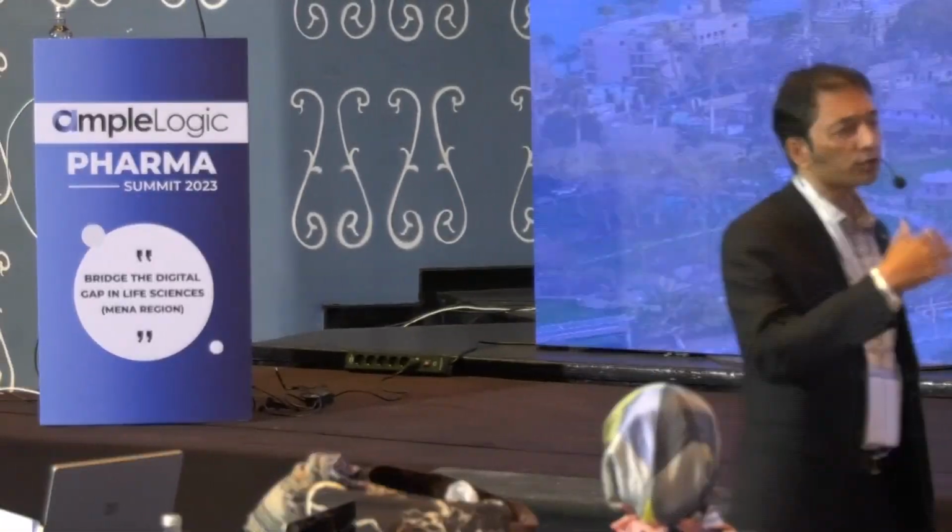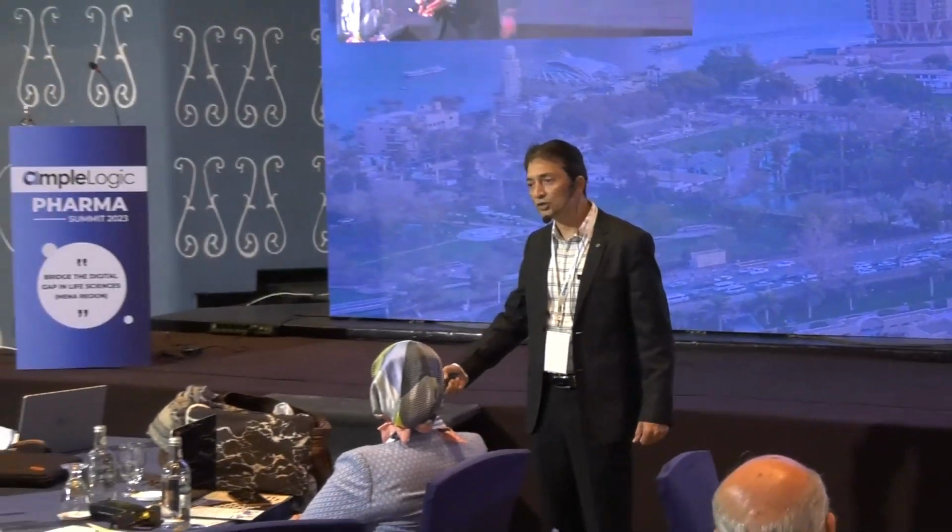One fine day, my production people came to me. They said, every day we are carrying lots of weight with us, because you have to weigh for the entire range. If you have to weigh 100 kg, you need to carry that much weight with you. One operator is engaged for at least a couple of hours doing the exercise. So what is the fun? Give us some way out. That was a trigger point for us to think in the direction where we arrived now.